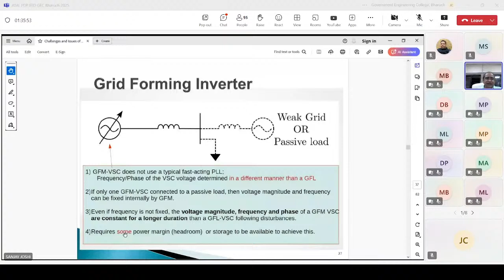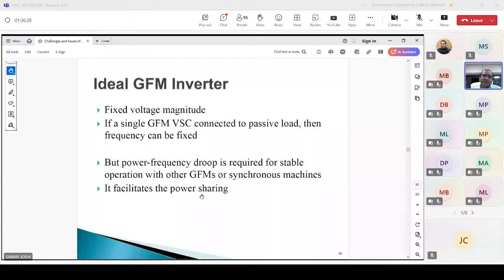Which is an ideal GFM inverter? It has fixed voltage magnitude. If a single GFM grid forming VSC is connected to a passive load, then frequency can be fixed. But power frequency droop is required for stable operation with other GFMs or synchronous machines. I'm sure the faculty members know about PF droop, right? That is a must for proper sharing of active power among the different GFMs and between GFM and synchronous machine. So that droop is very, very important.